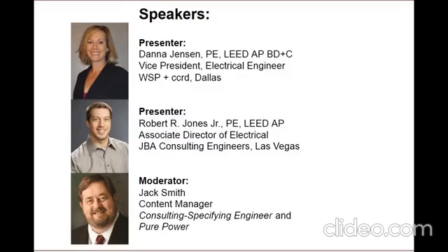In regards to connection to critical, that depends. In a hospital, if the smoke dampers are part of the smoke management system, they should be connected to the equipment branch. Otherwise, they can be connected to normal power. Building signage could also be connected to the equipment branch. There is a provision to allow connection of additional select power circuits to the critical branch deemed necessary to effective hospital operation. I have seen the critical branch used in a pinch to connect small power devices when there's no equipment branch nearby under this provision. But the intent is to minimize loads on the critical branch to reduce the chances of a fault. There may be a case to connect smoke dampers under this provision, but building signage is not really necessary for hospital operation.